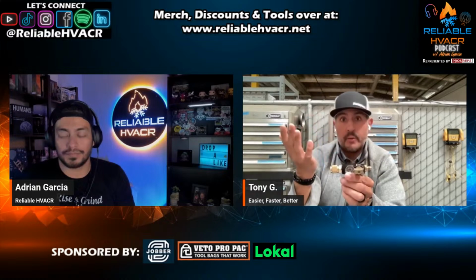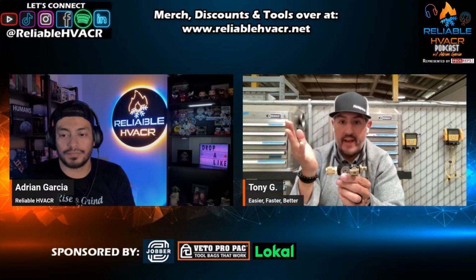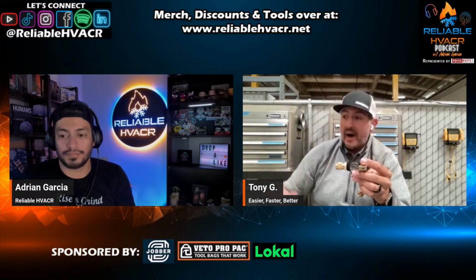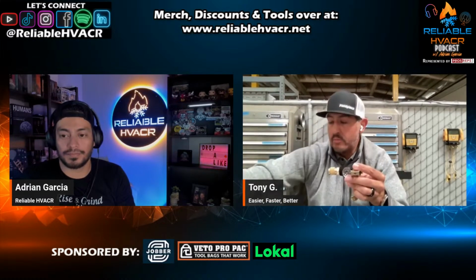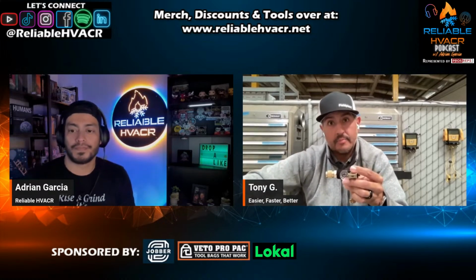Now, you perform the repair, whatever you had to do, it's time to put refrigerant back in, but you got to pull a vacuum, okay? Now, the best spot to measure vacuum when you're evacuating a system is at the system, right?